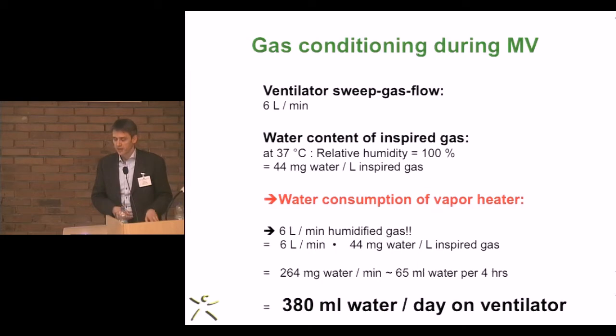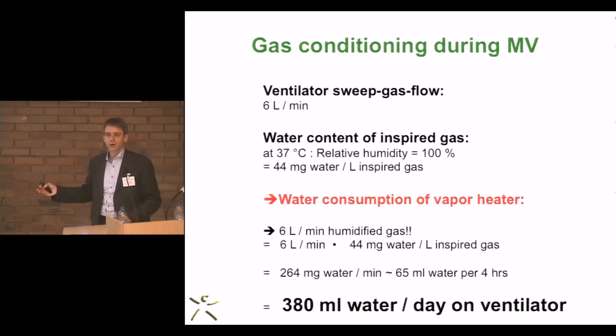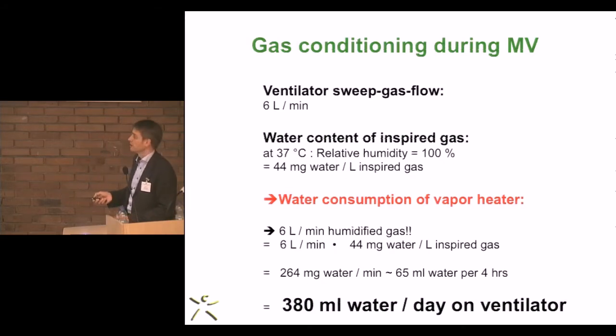And this is, from my point of view, actually the most important slide of the whole talk. And you take that home because you can actually control your heating humidifier by looking into the water consumption this device is using over time. And that's a very easy calculation if you assume that your ventilator has a sweep gas flow of about 6 liters per minute, which is more or less what you use in your ventilators.